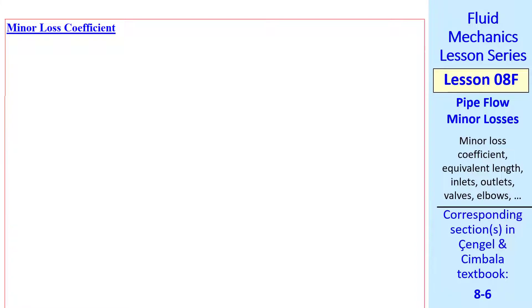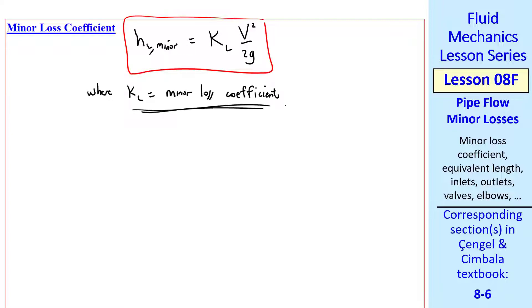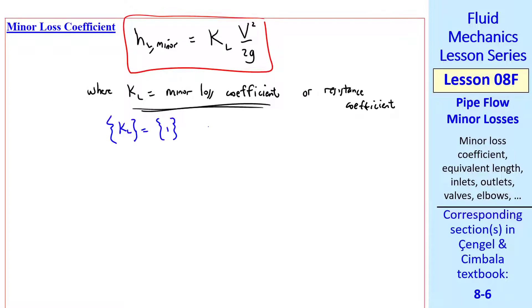The more popular way is with the minor loss coefficient. We define HL minor as some coefficient kl times v squared over 2g, where kl is the minor loss coefficient, which some authors call the resistance coefficient. The dimensions of kl are 1, it's dimensionless and unitless. I do some research in the HVAC industry, where they use C0 instead of kl, but they mean the same thing. I won't use this notation as resistance coefficient, but there is an analogy.